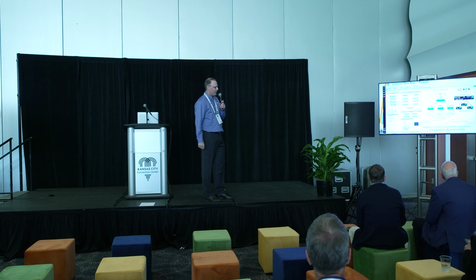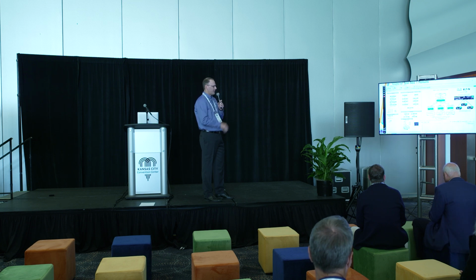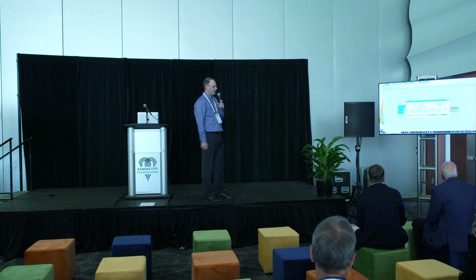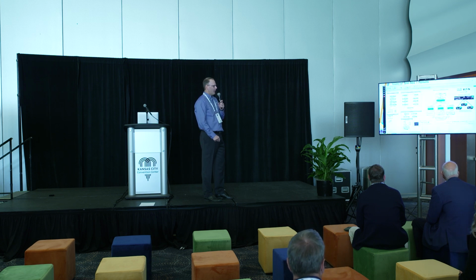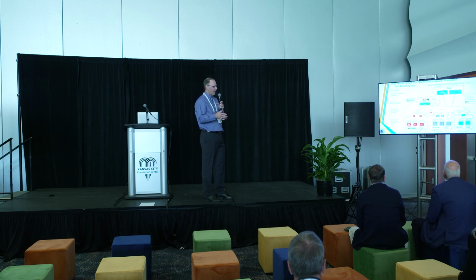And then we run the consensus algorithm, and this is where the peer-to-peer communication is enabled. The cap bank now is being turned on to inject reactive power. With the consensus algorithm, it's going to see that the battery energy storage system has some VAR capability, and it kicks in to compensate for the cap bank tripping off. So instead of the cap bank raising the voltage as normal, the battery is being asked to provide that capability. Normally a battery, being power electronics, is made to turn on and off constantly, whereas a capacitor bank is a discrete device with a limited number of operations. So there's a lot of benefit to leveraging multiple assets.